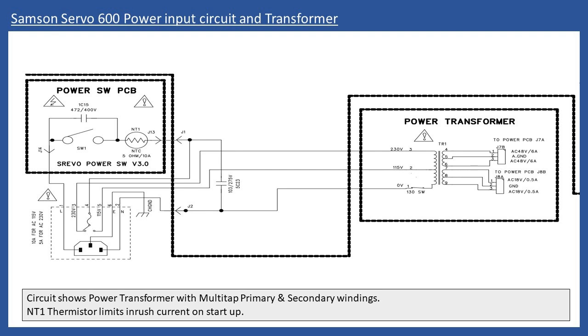The other thing you need to be careful of, depending on the type of amplifier you're working on, is that you may have a dual primary type transformer, or you may have a transformer like the one shown here for the Samson Servo 600. On the primary you have 3 wires. You have the 0, which is the neutral supply, you have 115 volts, and then 230.